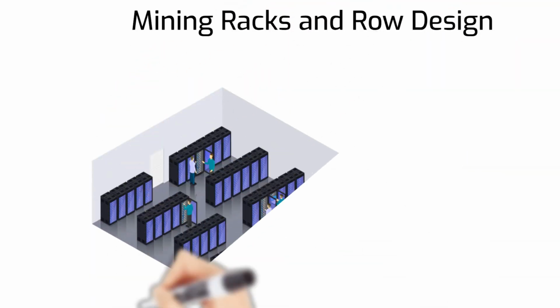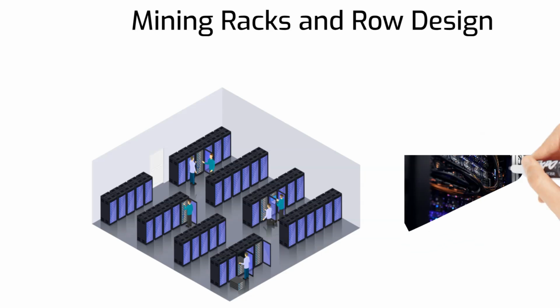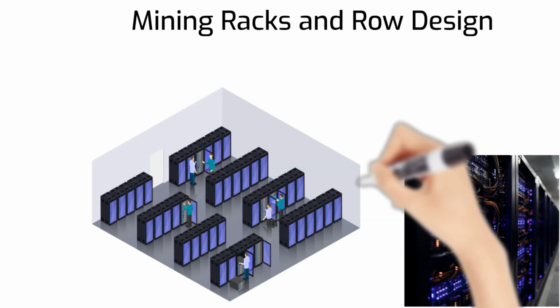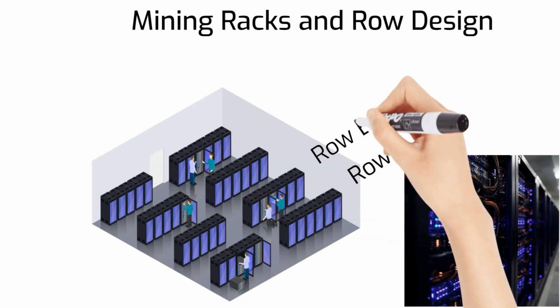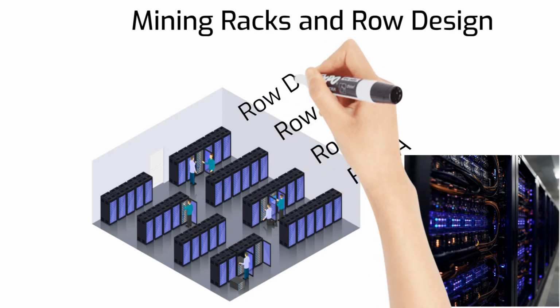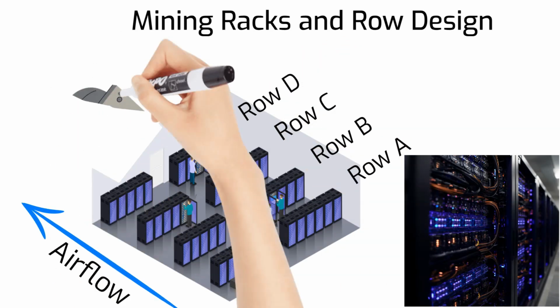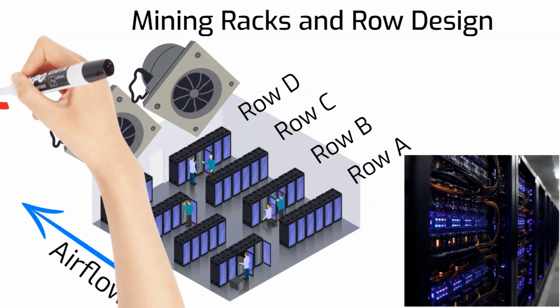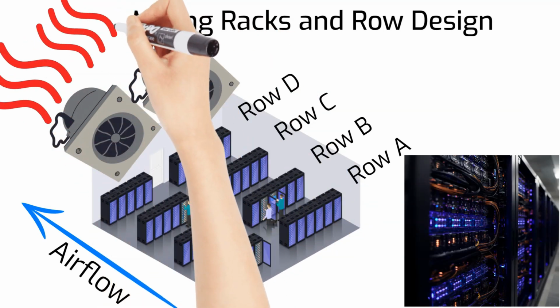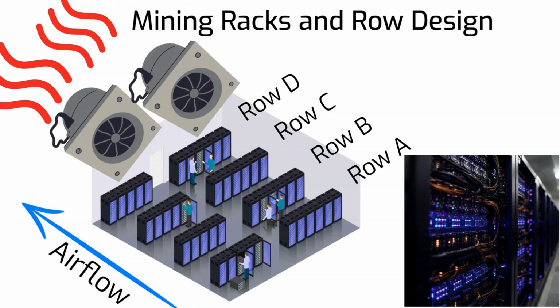Effective rack and row design for Bitcoin mining focuses on maximizing cooling efficiency and power distribution while ensuring accessibility and safety. Mining machines are usually installed on metal racks, stacked in long, uniform rows. This layout keeps wiring simple, airflow predictable, and maintenance fast. Most miners pull cool air from the front and eject hot air out the back. That means row orientation matters. Every rack must align with the cooling system, or heat builds up quickly. Ensure adequate space between rows and around individual racks for easy access during maintenance, upgrades, and cable management.